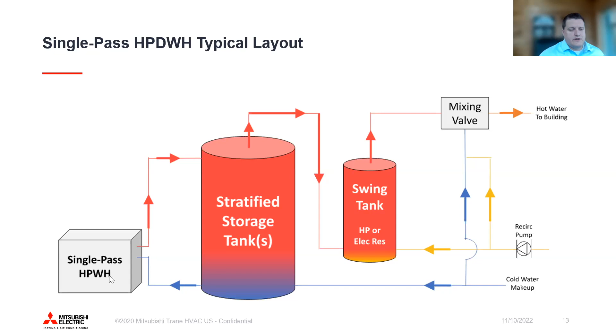So we've talked about a lot of this throughout that last slide, but when you look at these types of systems, whether it's our single pass system or a multi-pass system that are out there in the market, you really have a whole different concept in how you're designing the system. With a boiler, it is fairly inexpensive to do N+1 or to make the plant very large to overcome any unknowns in the building load and things like that. With any of the heat pump systems, because their recovery rates can be a little bit lower, it is really important to look at the storage piece.